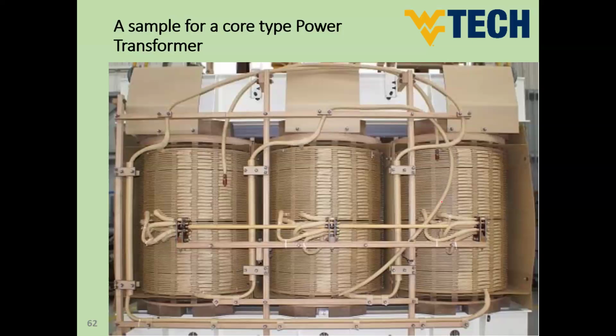Actually, all of these transformers, you know, have core loss and copper loss. So how can we dissipate these losses? Because these losses by the end will be converted to heat. If you don't dissipate this heat, it would accumulate inside the transformer, and this may burn the insulation and burn the windings of the transformer itself. So we have to dissipate this heat one way or another in order to avoid burning our devices. We will see how to cool a transformer in a few slides. So this is one shape of our transformer.